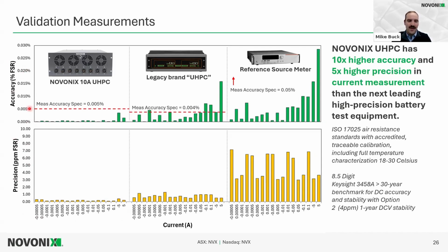So we specify specifically with our measurements, we try to follow the ISO guidelines and do a 4-to-1 ratio, to make sure that when we're doing our expanded uncertainty and our measurement uncertainty, it falls within a 4-to-1 ratio of what you're measuring. So that's why when we specify, you can see that all of our measurements fall under the certain accuracy specification. Whereas if we look at our competition, you can see their specified accuracy doesn't quite fall under the same line. So basically we can tell that there's a little bit of too tight of a tolerance that's been set for their specifications. And as you can see, the reference source meter has a specification set where their measurement accuracy is quite conservative, and we can tell that everything falls within that.